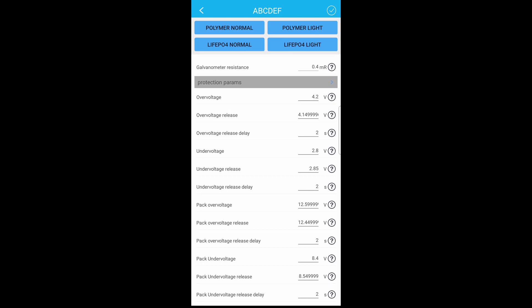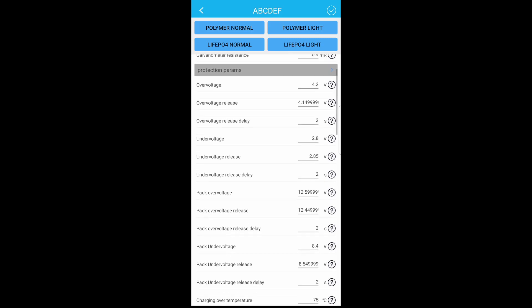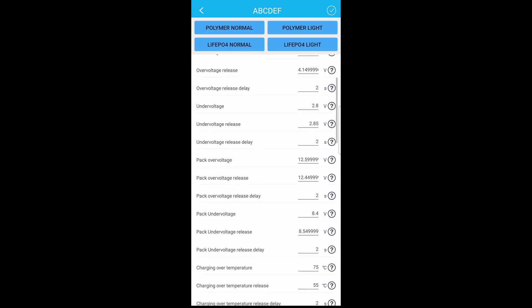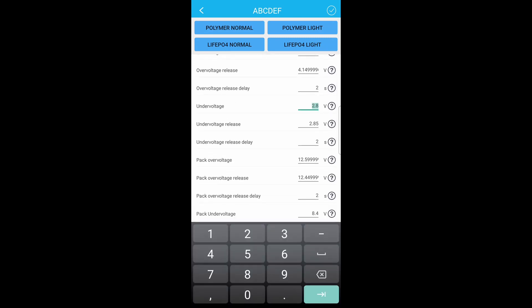Under voltage release, I like to change. So my under voltage I'm going to change to 3, and then this under voltage release 3.5.